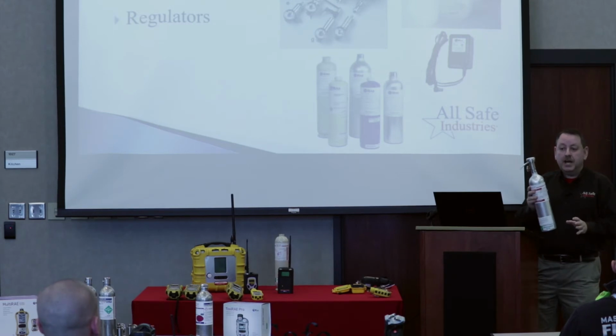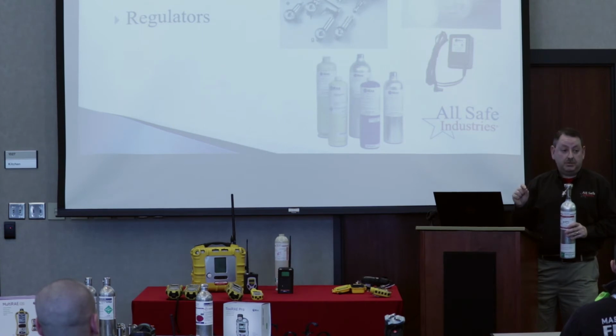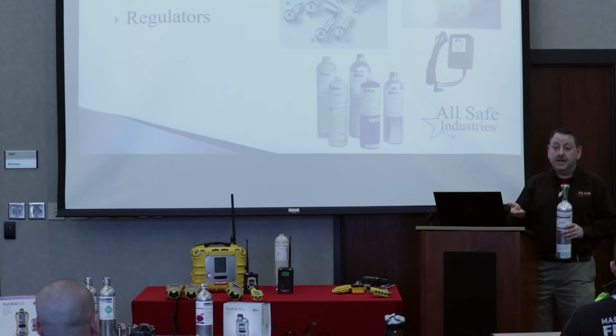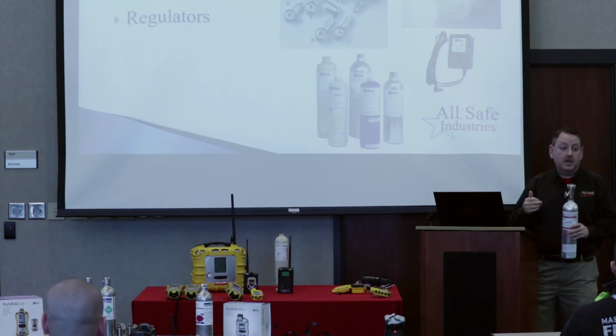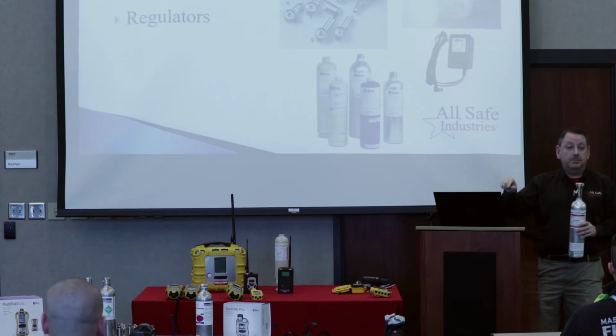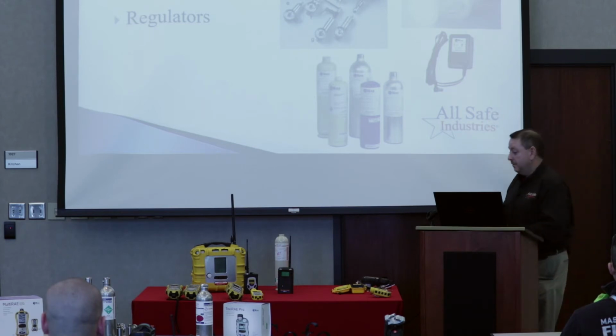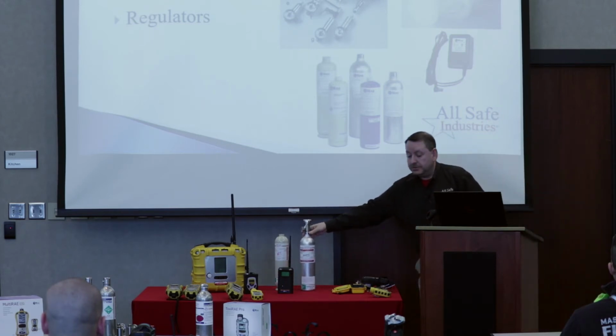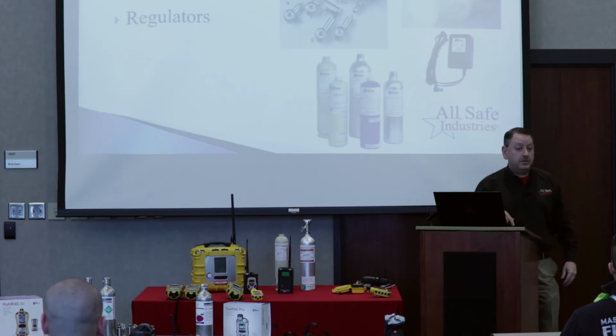The biggest thing we're watching out for when you're doing that bump check is you're putting gas on a meter and a sensor sits at 0. It's very dangerous, because what's to say that you're not dropping your tubing into a confined space and getting some gas to the sensor? We want to know that sensor's not going to read gas before our life is in jeopardy. So you always want to do the bump check to make sure that the sensors are reading properly. And again, you guys purchased the AutoRAE 2 calibration cradle, and it's super simple. All you have to do is hit the bump button, and it will run the bump check for you. Okay? And remember, you need a cylinder for each sensor that's in your instrument.